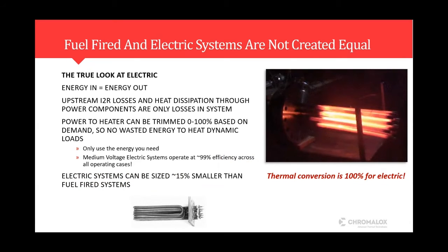On the electric side, we know that thermal conversion of electric systems is 100%, meaning all of the power that's applied to that heater is converted into heat. That doesn't mean there aren't losses. The losses that we see on the electric side are upstream, in your I²R, and that's typically losses through your power wiring, and then also heat dissipation through the power components. But despite those losses upstream from these electric systems, it still only factors in a few percentage points of losses. And that's why we saw, earlier in that slide, about 95, 96 on low voltage and upwards of 99 on the medium voltage.